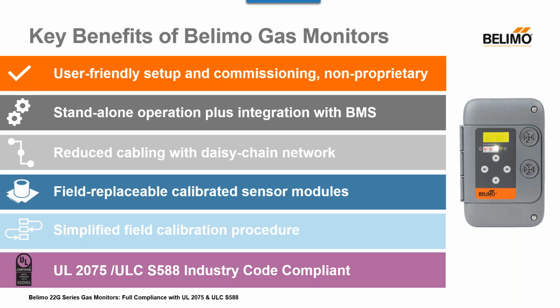Finishing off, key benefits of Belimo gas monitors: user-friendly, easy to commission and service, standalone operation or the ability to integrate into a BMS, cost savings through one monitor measuring up to 2 different gases, reduced hardware, redundancy of needing a dedicated expensive control panel, and the ability to daisy chain wiring for reduced installation costs, the convenience of factory calibrated field replaceable sensor modules or simplified calibration procedures on site, and peace of mind with UL 2075, ULC-S588 industry code compliant devices.